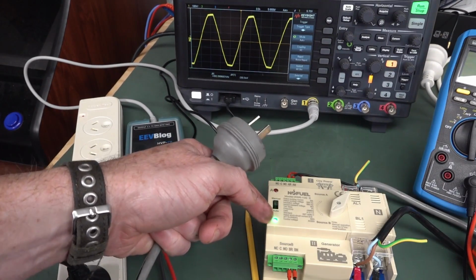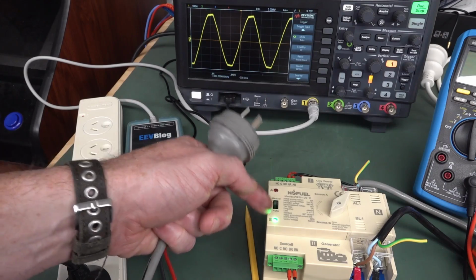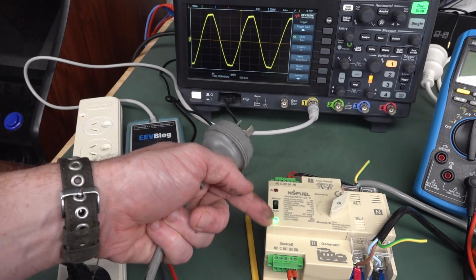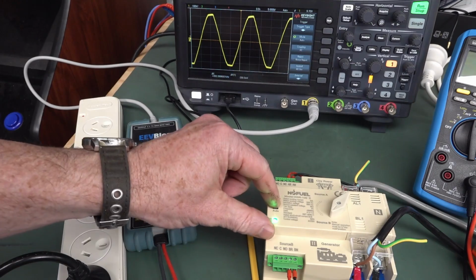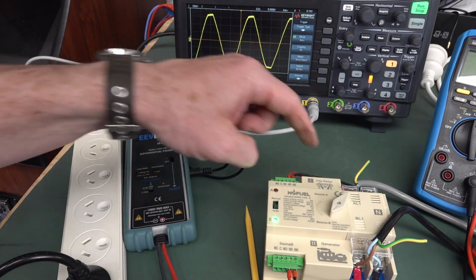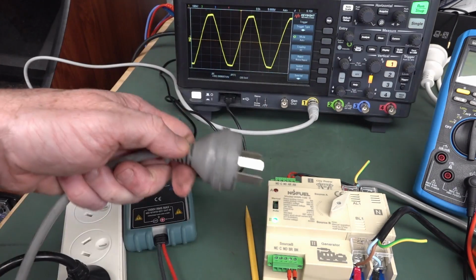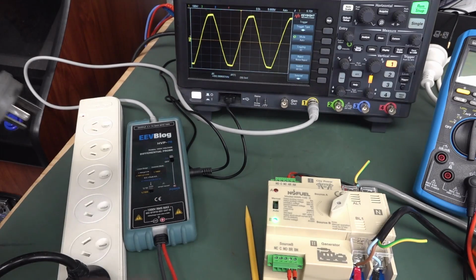It looks like this just indicates, not which one's on, just that there's actually power active there. Now, if we switch this back to auto mode, the priority input should be this city one, this grey one. At the moment it's back to the generator, but it should switch back.